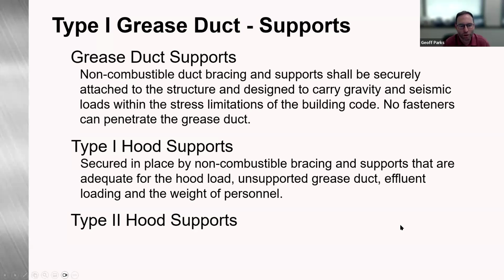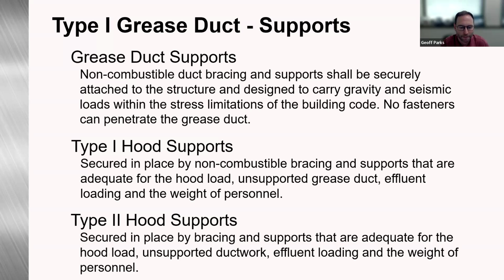And then Type 1 hood supports. So this is going to be secured in place by non-combustible bracing and supports that are adequate for the hood load, unsupported grease duct, any effluent loading, and the weight of personnel. And then Type 2 hood supports are secured in place with bracing and supports that are adequate for the hood load, unsupported ductwork, effluent loading, and the weight of personnel as well.